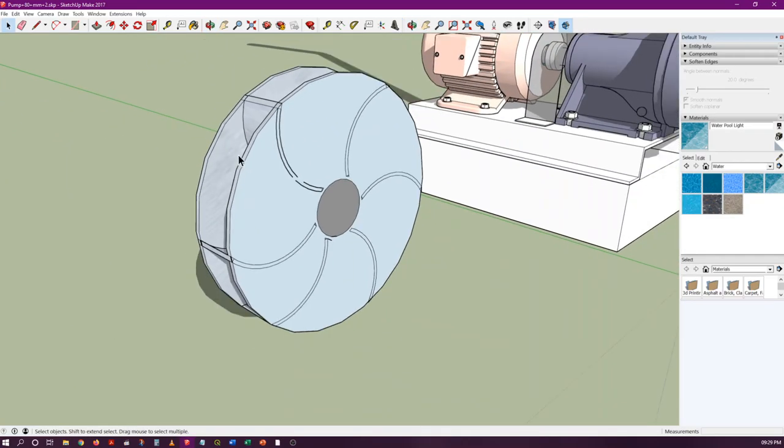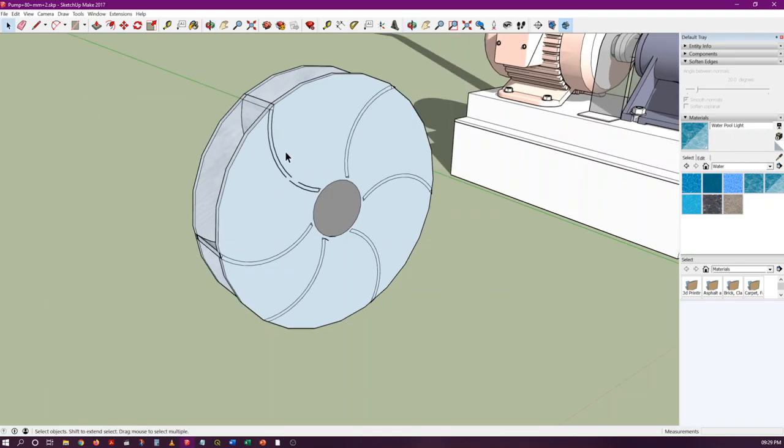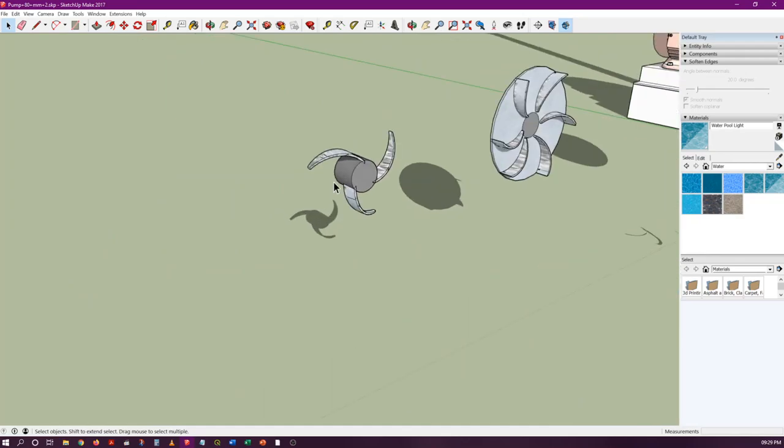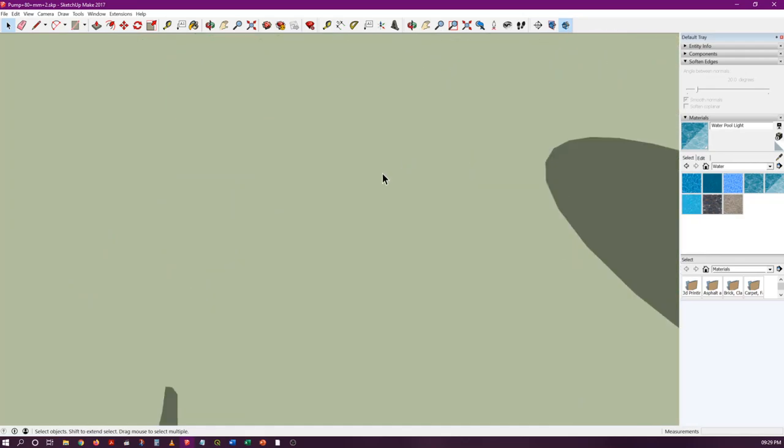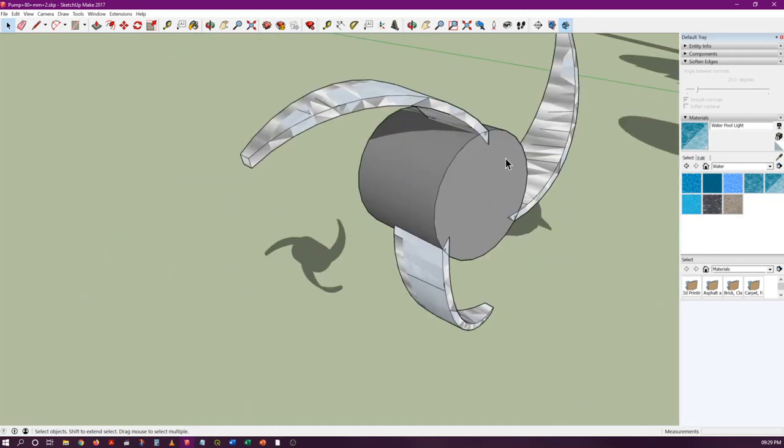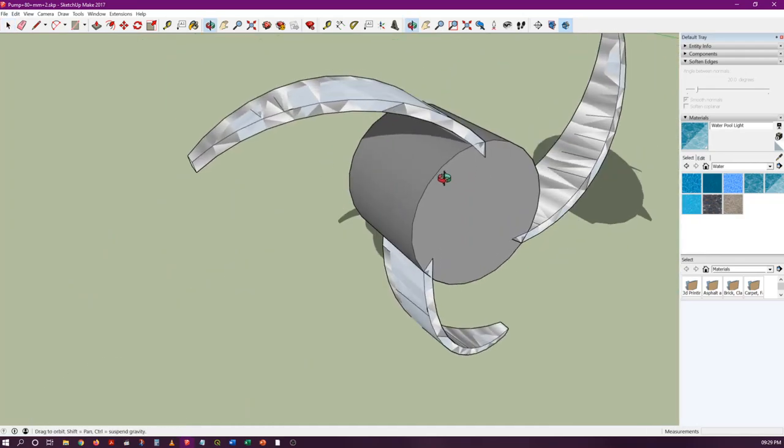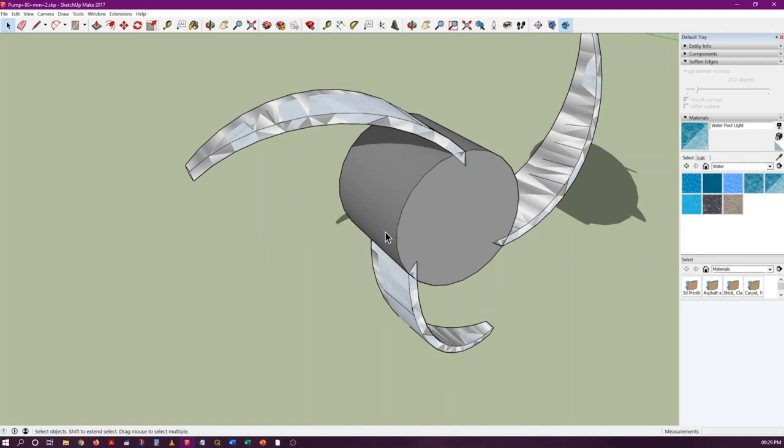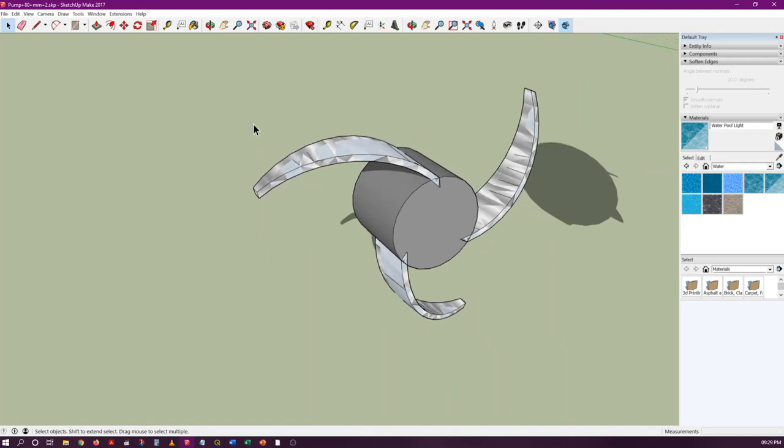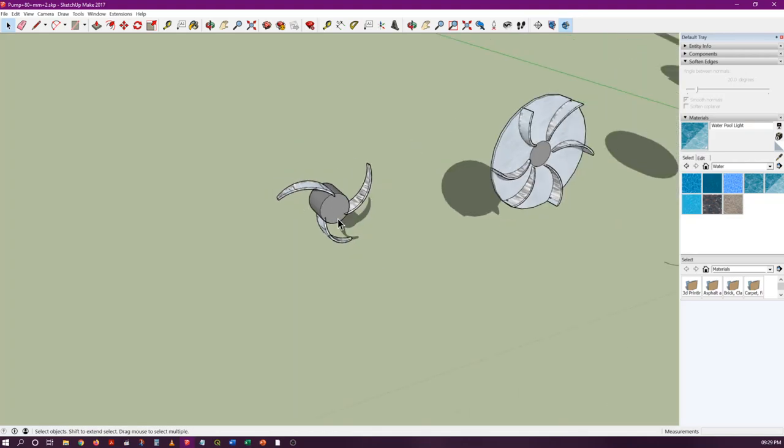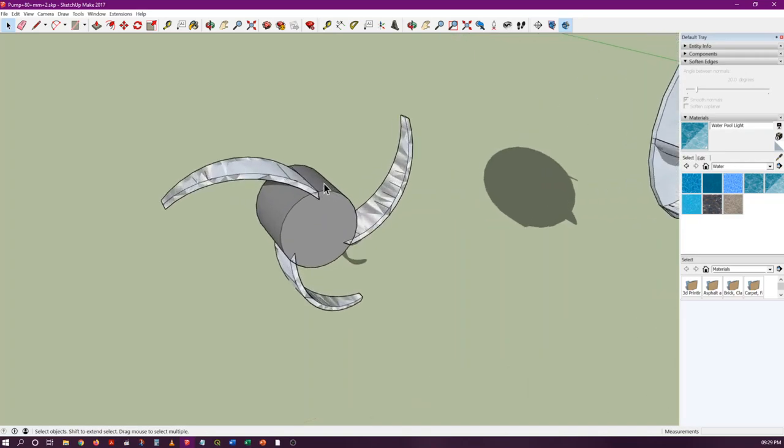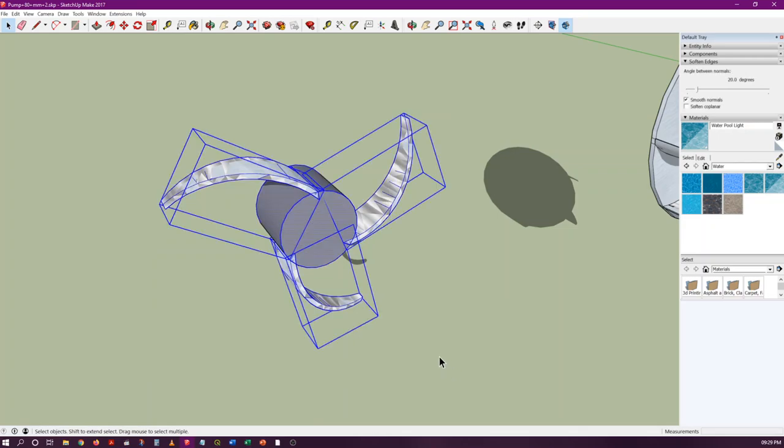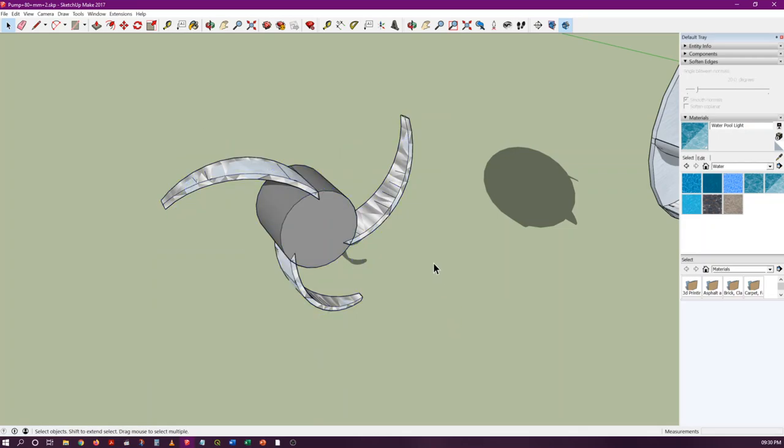At the other end, we have this kind of open impeller where the blades are simply connected to this central hub and they simply rotate inside. This has its own utility, although its efficiency is less, because when you have to pump very impure fluids or fluids having sludge-like behavior, it is very useful.